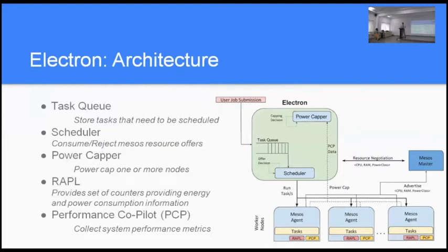But for data centers, it'll really make sense to tell the utility company that, by the way, tomorrow between 2 p.m. and 5 p.m., my cluster will not breach this particular power envelope. If a cluster can give that guarantee to the utility company, the utility company can plan and say, okay, this is the power draw that will come from this data center. So our research is focused on how we can keep the power envelope contained, because we have a mechanism of bringing down the power of each node. So we're dynamically trying to understand how much the machine is being used and try to bring it down.